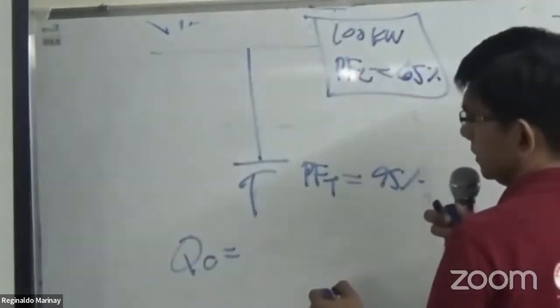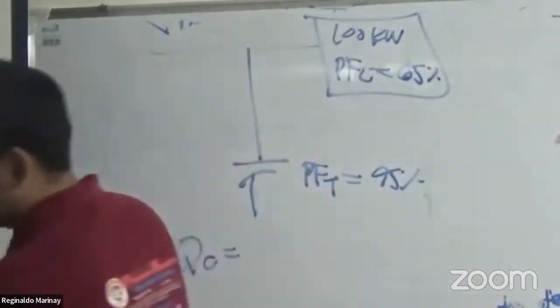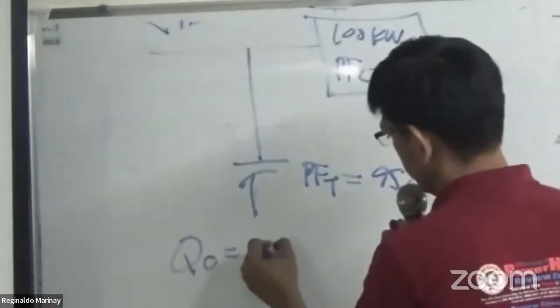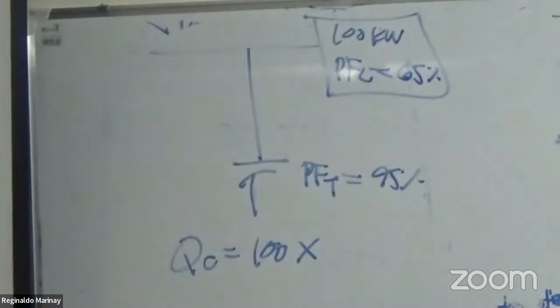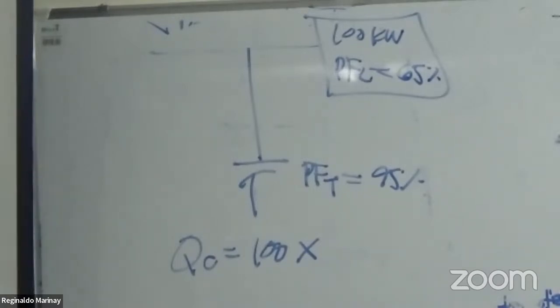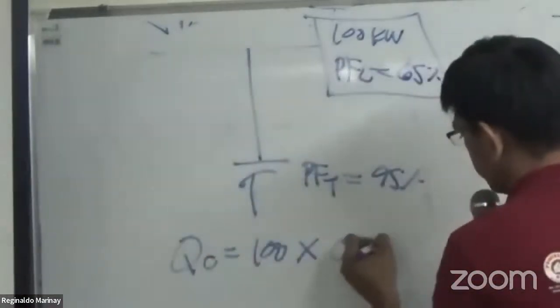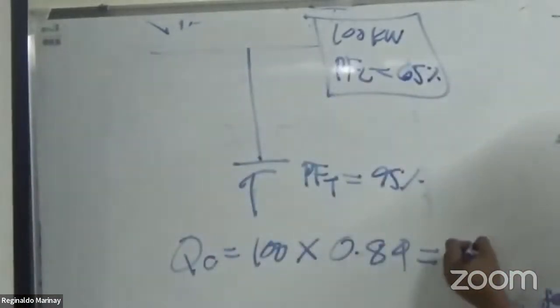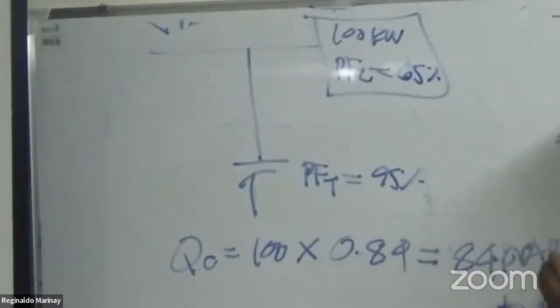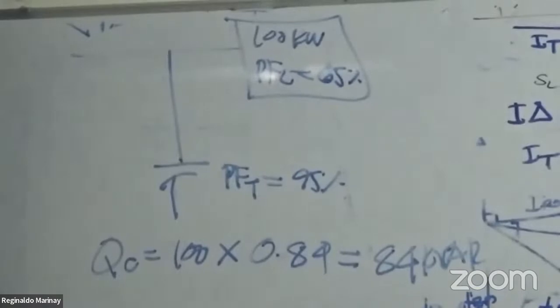So your Q of the capacitor is equal to the power, the 100 kilowatt, multiplied by a value. Initially we had 65, corrected to 0.95, so you come up with a multiplier. How much is this? This is 0.84. So therefore this is 84 kvar, that is the size of the capacitor you're going to buy.